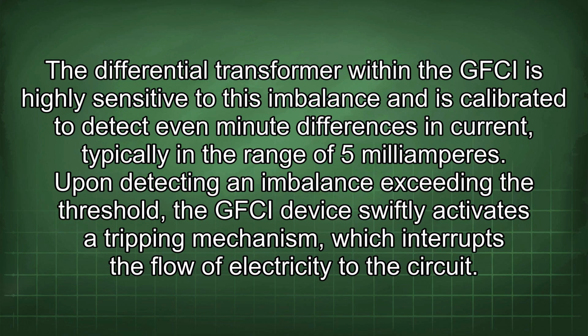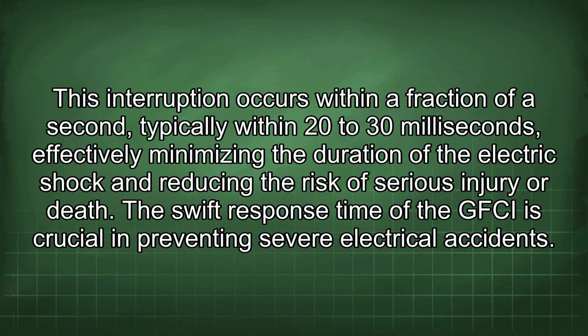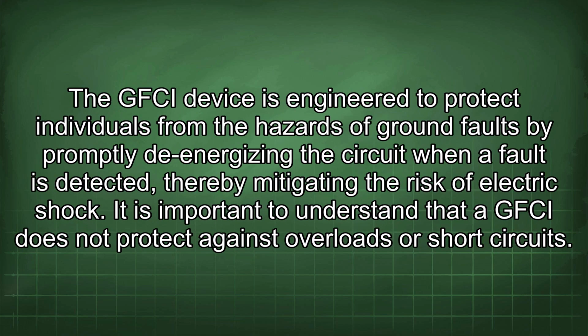Upon detecting an imbalance exceeding the threshold, the GFCI device swiftly activates a tripping mechanism which interrupts the flow of electricity to the circuit. This interruption occurs within a fraction of a second, typically within 20 to 30 milliseconds, effectively minimizing the duration of the electric shock and reducing the risk of serious injury or death. The swift response time of the GFCI is crucial in preventing severe electrical accidents. The GFCI device is engineered to protect individuals from the hazards of ground faults by promptly de-energizing the circuit when a fault is detected, thereby mitigating the risk of electric shock.